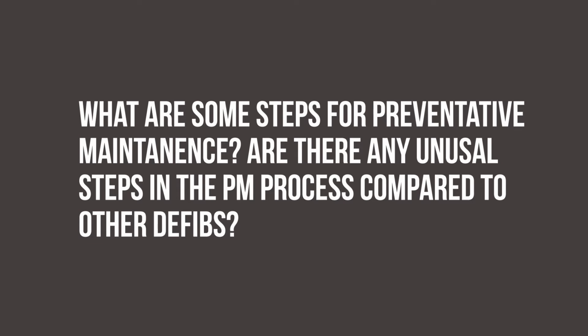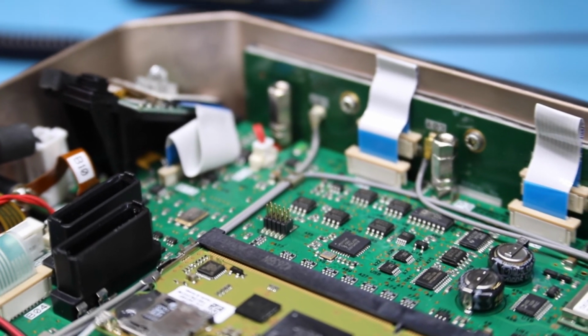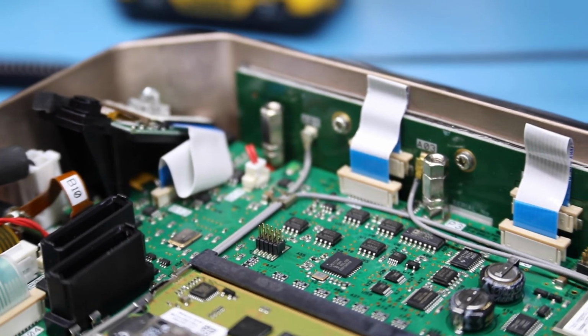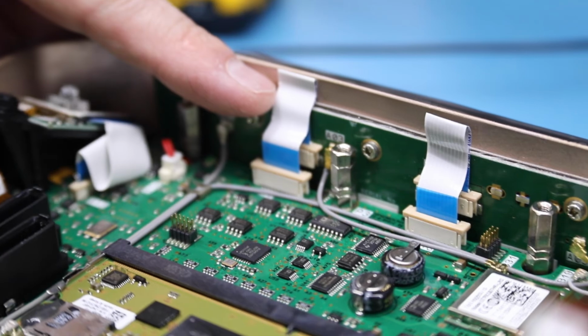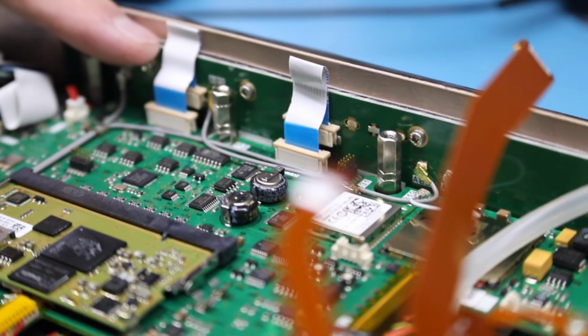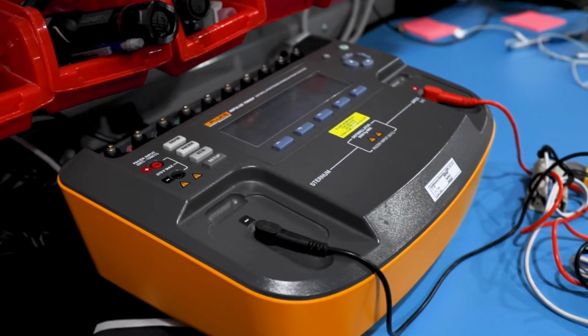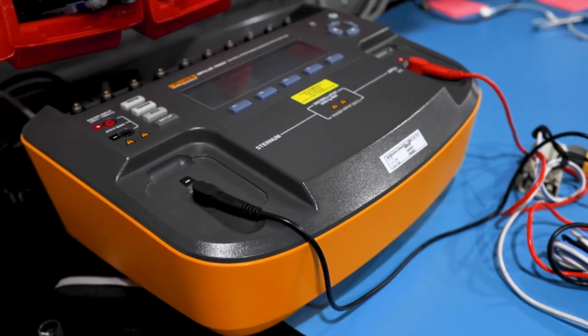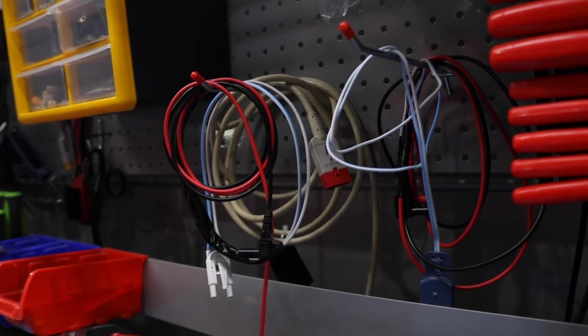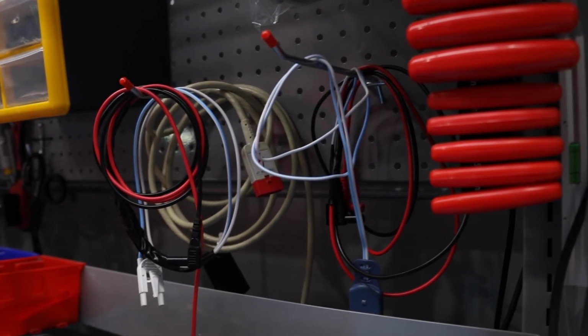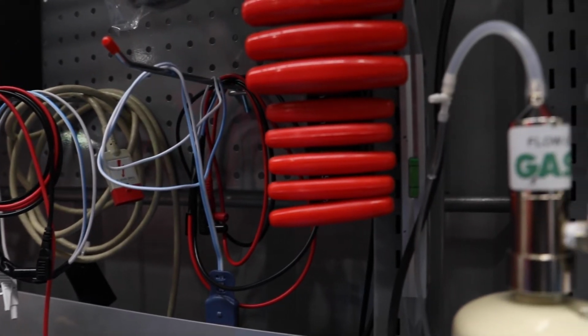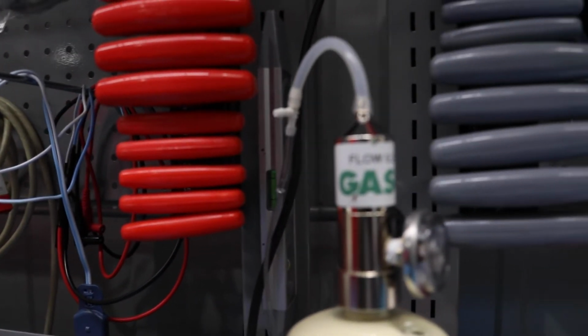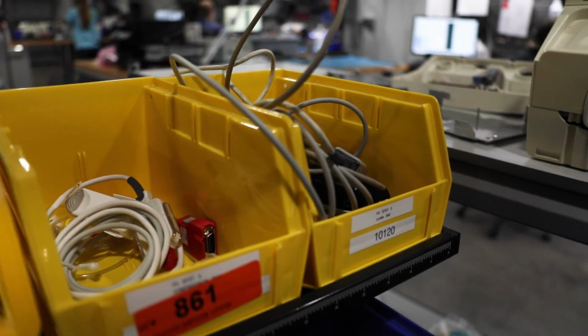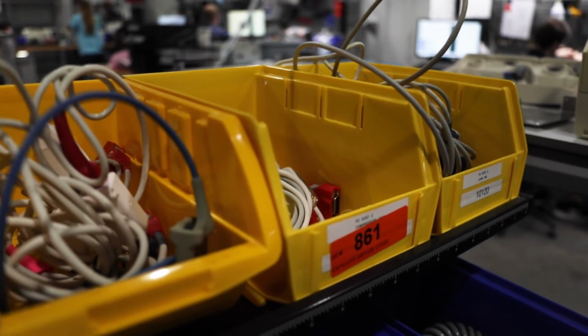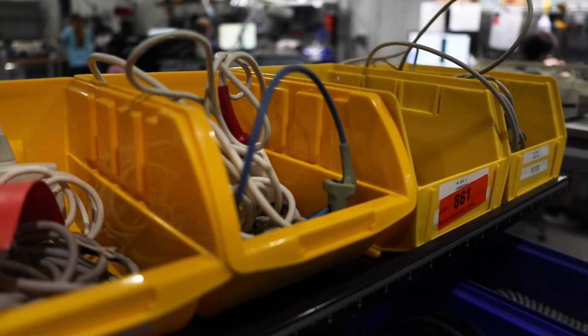The preventative maintenance for the Tempus is a bit longer than most monitors and DEFIBs. Every function has an extensive calibration procedure to ensure state-of-the-art monitoring accuracy. The manual has detailed instructions for the entire PM process and extensively covers every parameter. The PM process for the Tempus is very similar to most other DEFIBs, but with a few additional steps. PMs are essential to maintain accurate calibration, ensuring the unit delivers precise patient data to medical personnel.